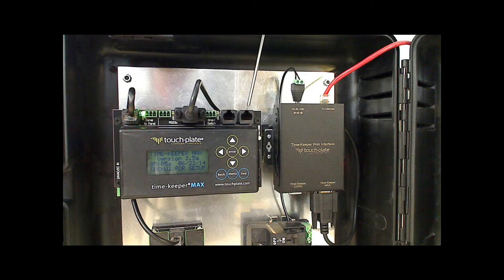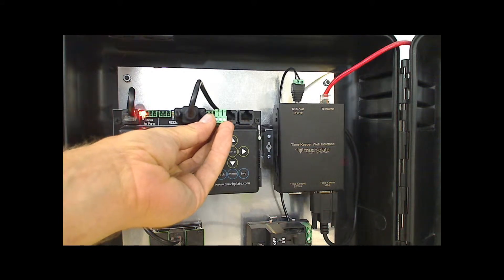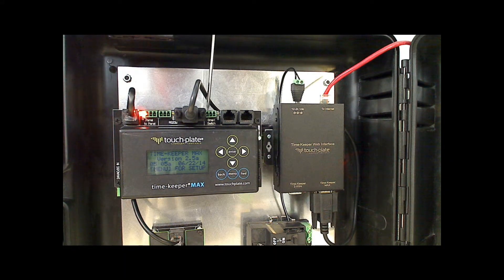The last three positions on the Timekeeper are for the smart switch RS-485 network. Using the 3-position male Phoenix connector, terminal 1 is for the ground or the shield, terminal 2 is for the minus, and the last terminal is for the plus. The two RJ-45 jacks take the standard Cat5 patch cable and both pass power and communication through.